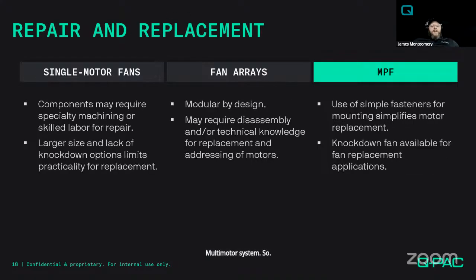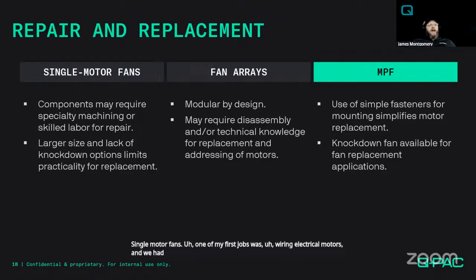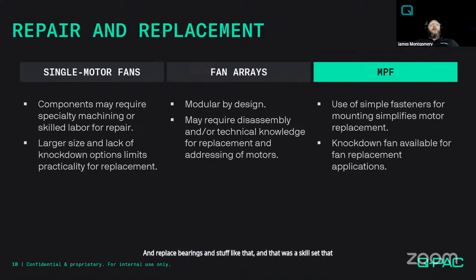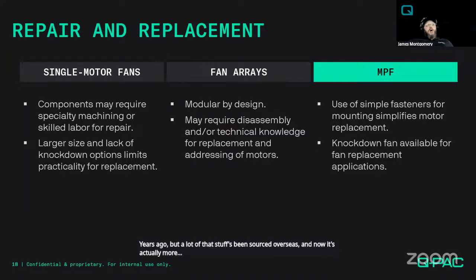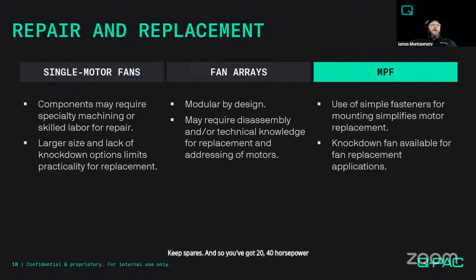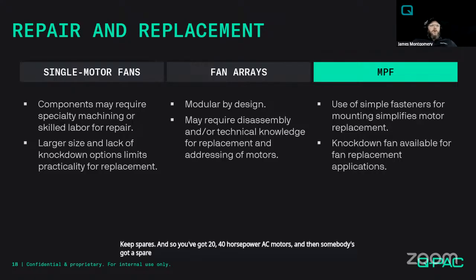So repair and replacement, I keep getting ahead of myself. Single motor fans. One of my first jobs was wiring electrical motors, and we had a machine shop and rebuilt shafts and replaced bearings and stuff like that. And that was a skill set that was pretty common years ago. But a lot of that stuff's been sourced overseas, and now it's actually more cost efficient and easier to just keep spares. And so you've got 20, 40 horsepower AC motors, and then somebody's got a spare 40 horsepower motor on a shelf somewhere or in a space somewhere.